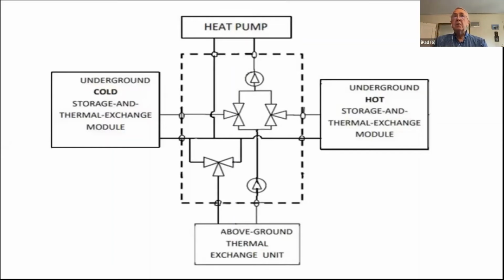So here's an example which is quite a bit simpler in terms of the number of valves that we had for the Belgian design. It does have 2 water pumps, and it has 3 valves. The things with the triangles are 3-way valves, and everything is going to be computer controlled here. We'll be able to control the pump flow rate for those 2 pumps individually, and we're going to control the valve settings so water can flow from one side to any of the other sides on those valves.